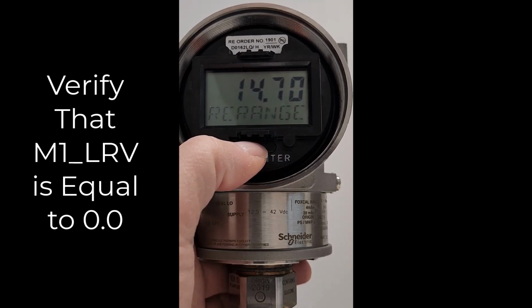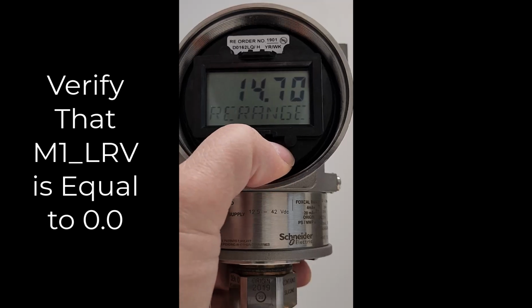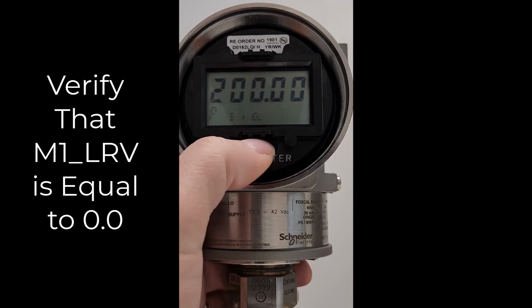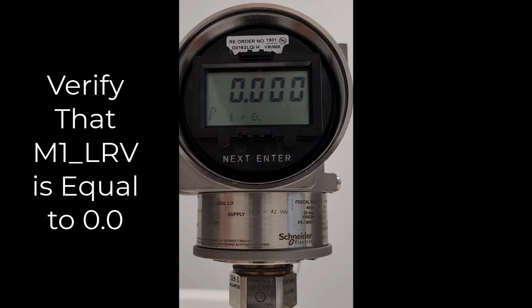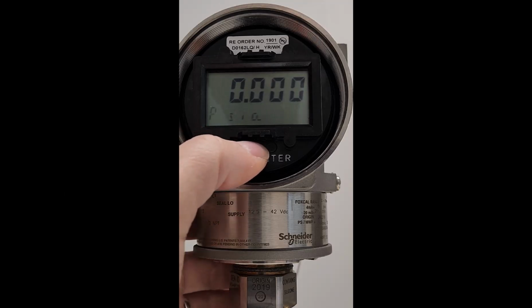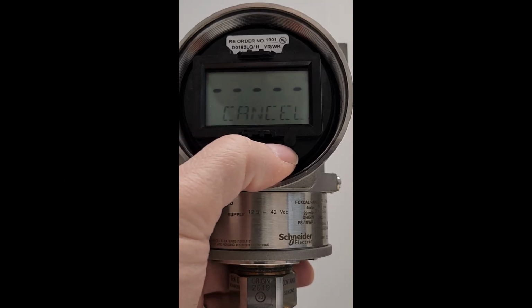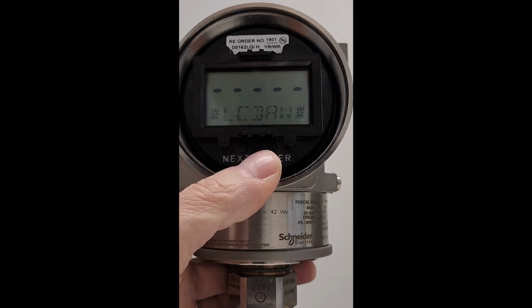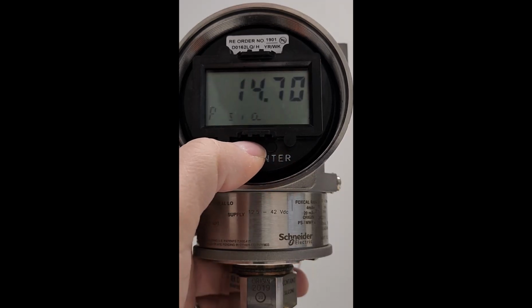Simply press the next button, you'll see rerange, press enter, you'll see the M1 URV, press next, and you'll see the M1 LRV. We want to make sure that this is configured to 0. In this case it is. If it was not, we would change it, but it is here, so I'm just going to press next. I'll see cancel, press enter, I'll be back to the measurement display.